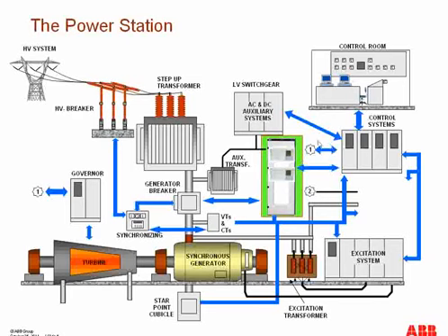We have the control systems, then we have the AC-DC auxiliary system, and that system is being fed by the auxiliary transformer. We have a generator breaker over here, and then we have the GSU, generator step-up transformer, for the generating station, and then the GSU is connected to the high voltage transmission system. So this is the overall structure of a power station shown in this picture.